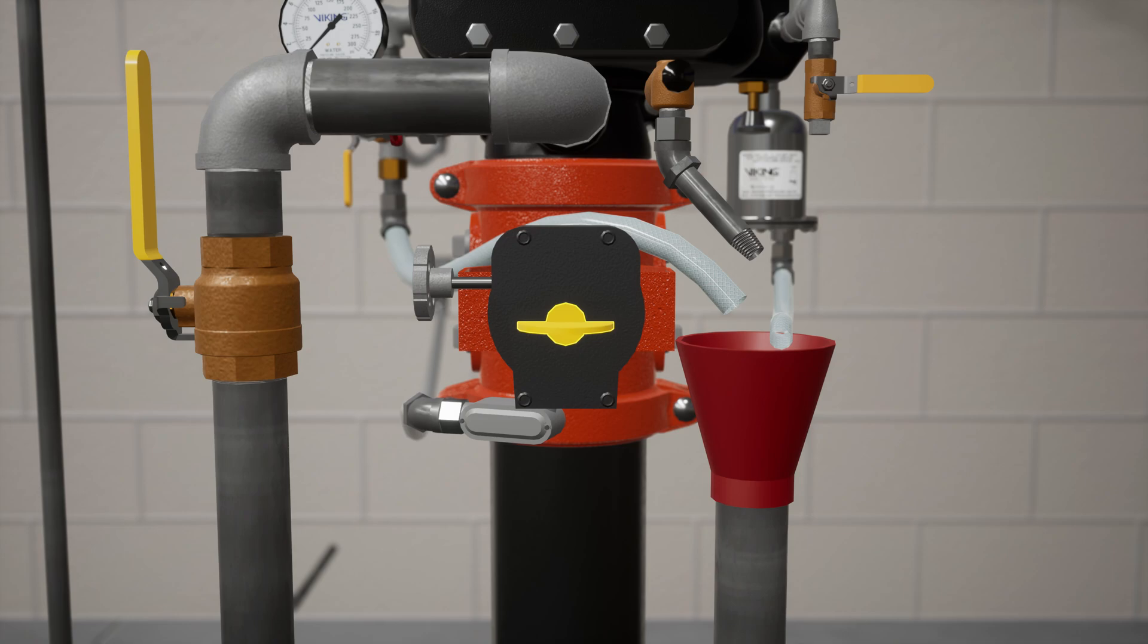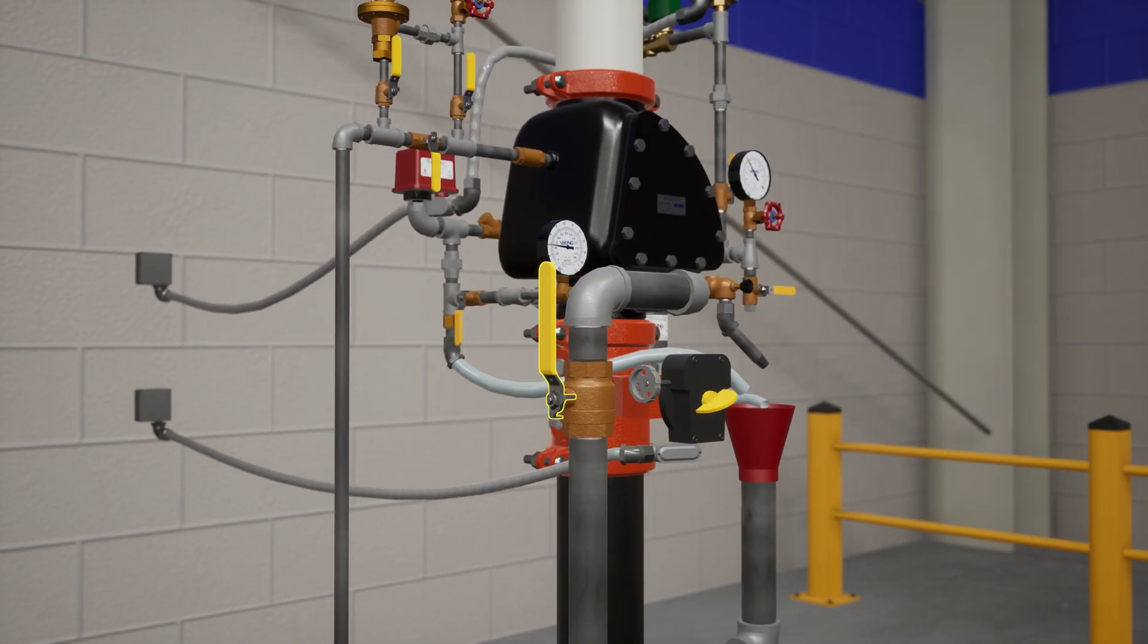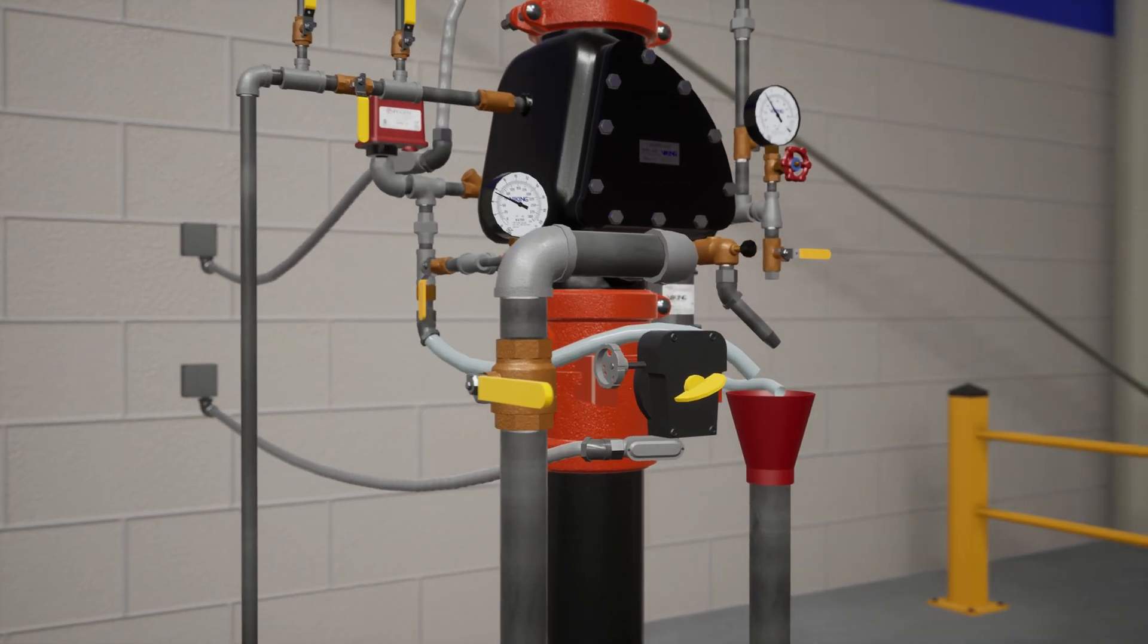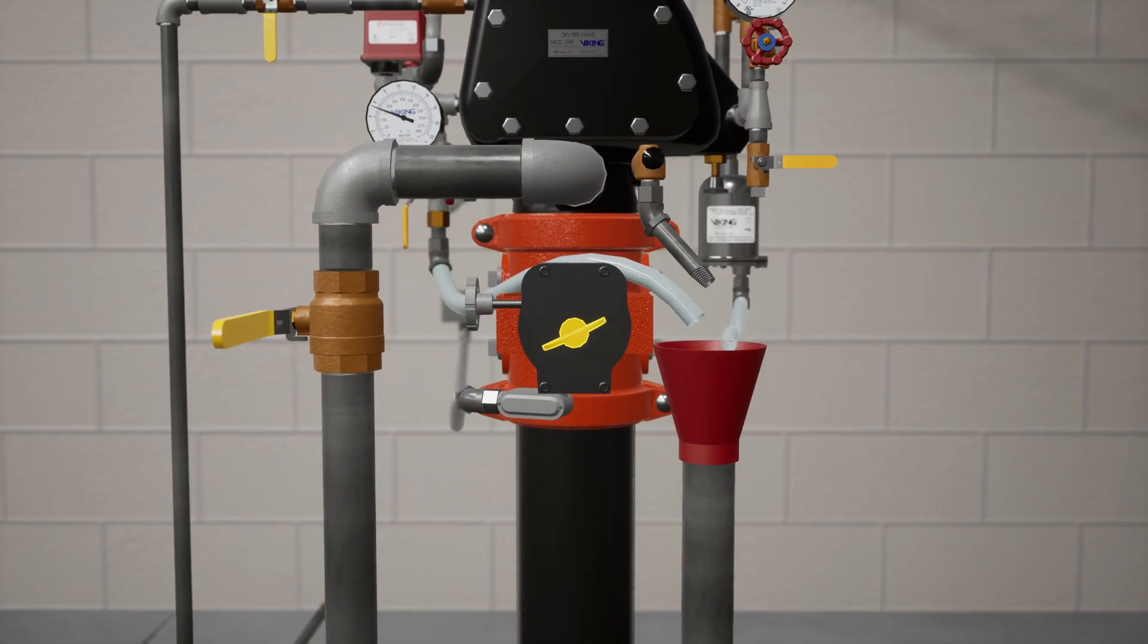Partially open the water supply valve and allow water to enter the inlet of the valve. Now, close the main drain. Water supply pressure will show on the water supply pressure gauge. Fully open the water supply control valve.